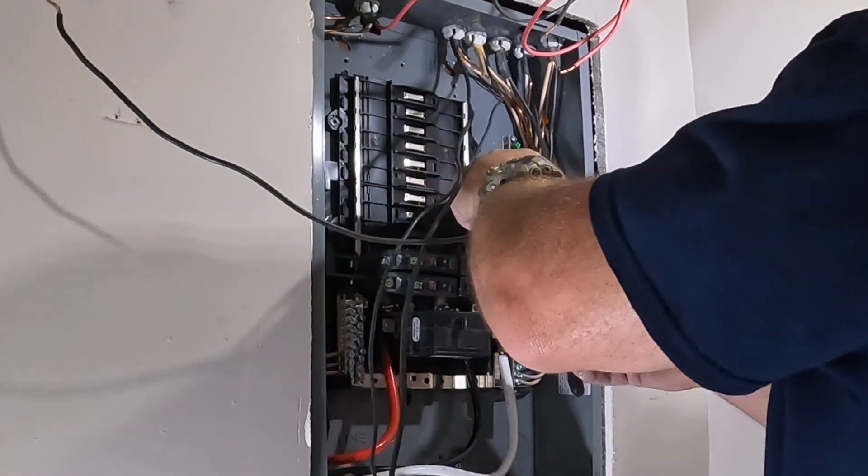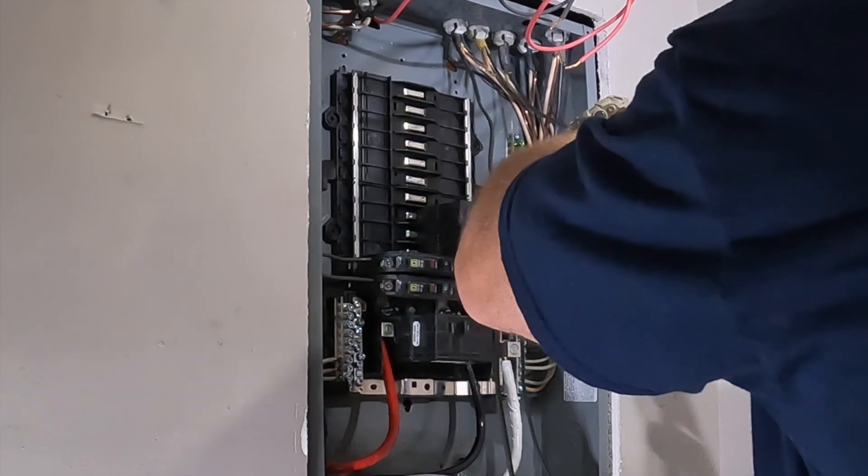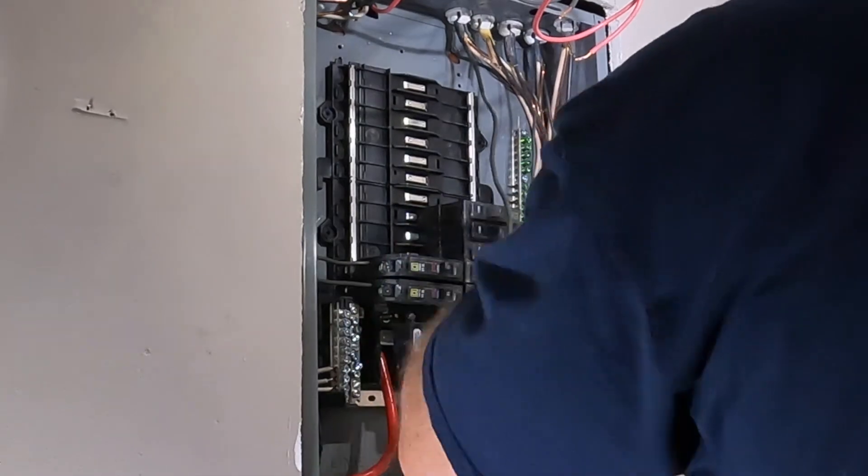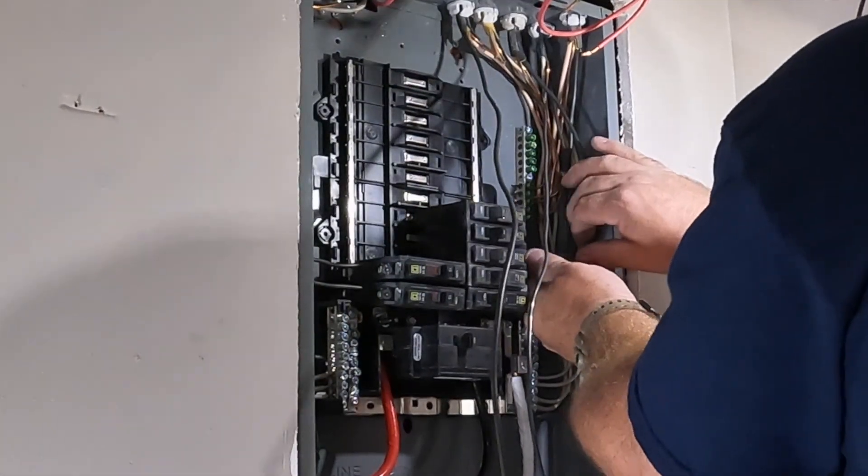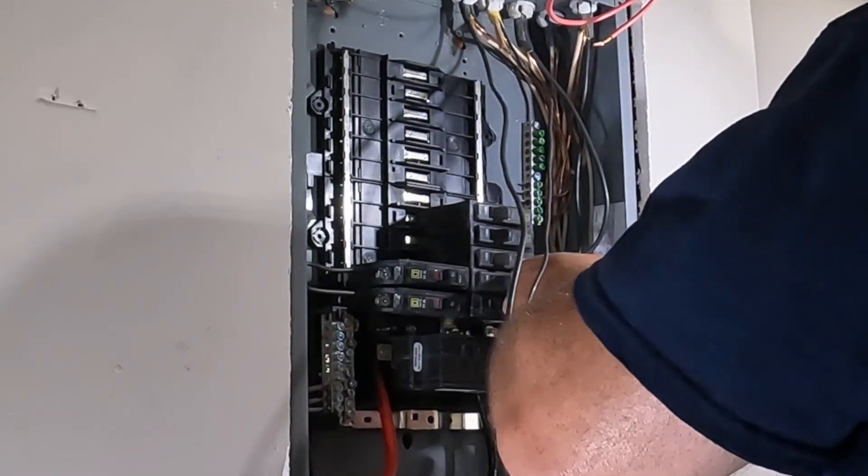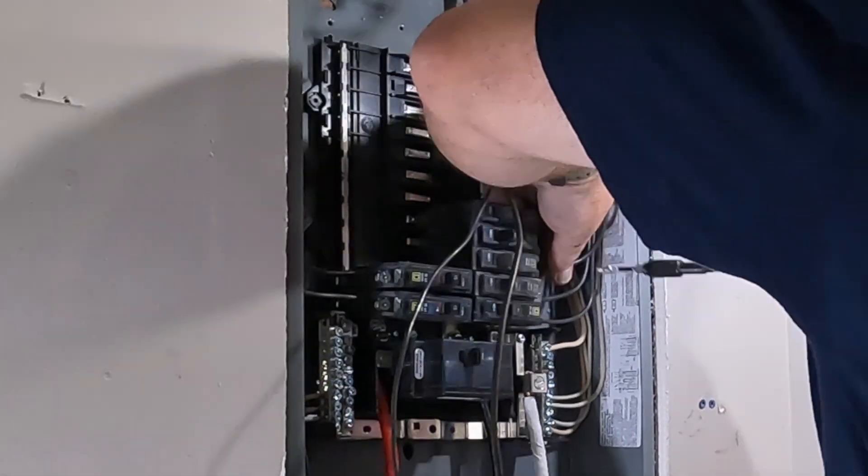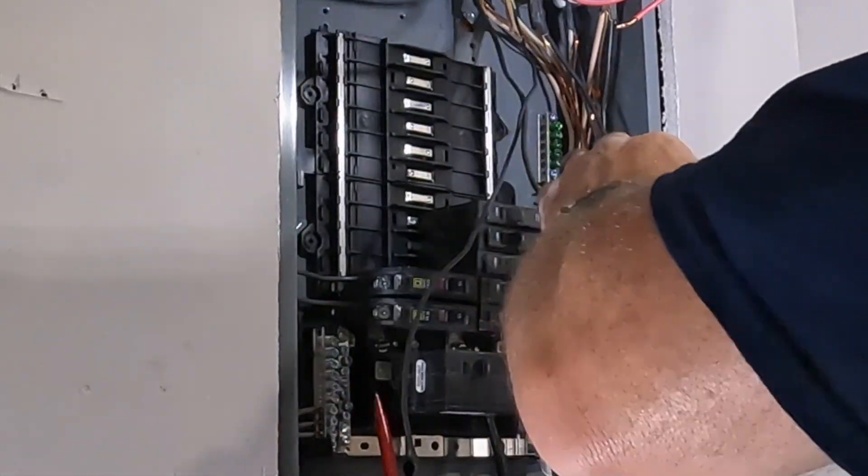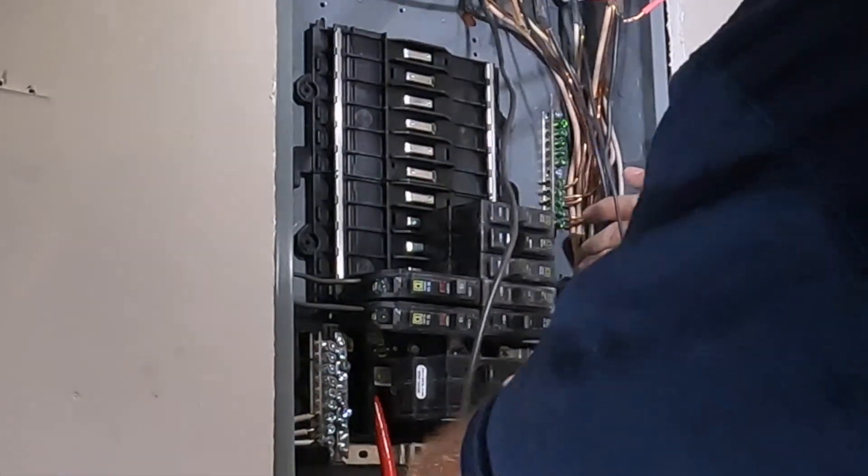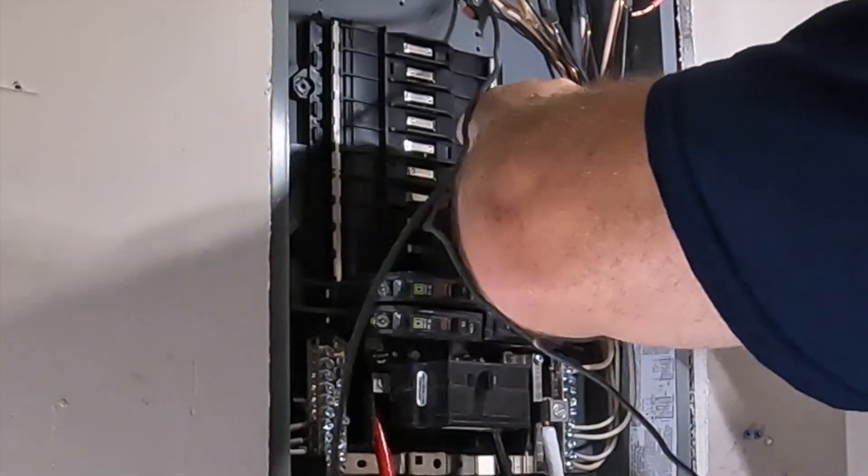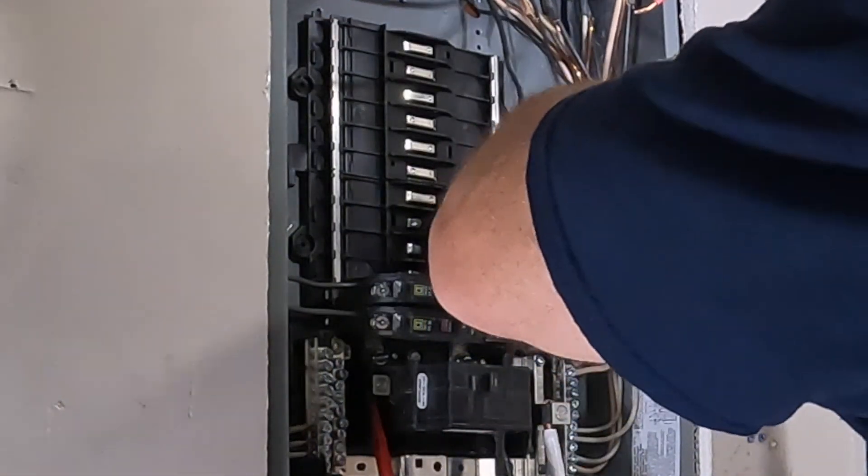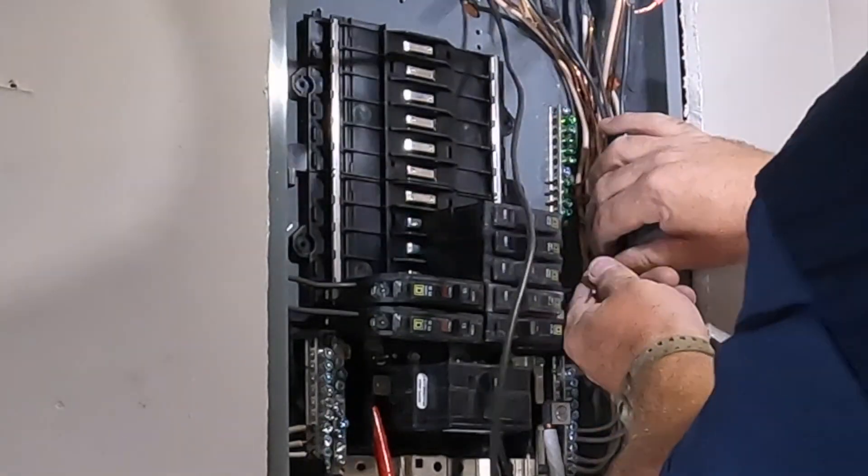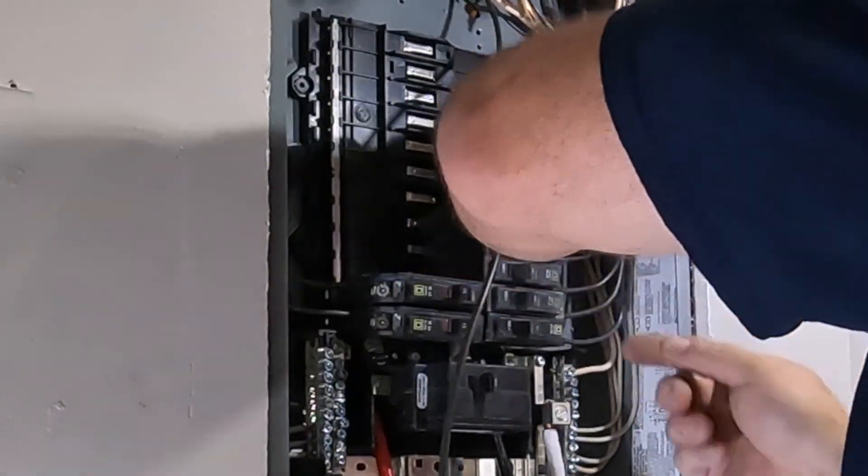I really like working with these QO panels, but as you can see here normally the main circuit breaker is on the top, but the conductors that were in place, the feeders, they weren't long enough. So I had to put this panel in with the main breaker at the bottom. Again, I should stress that this is not the main breaker at a main disconnect, this is a sub panel. Nonetheless, the feeder conductors were not long enough to put that main disconnect up at the top of the panel. So that's why it's at the bottom. But as you can see, those neutral terminals are right beside where the main breaker is, and if that's at the top of the panel and your branch circuits are coming in from the top of the panel, that makes for terminating your conductors very easy. So that's one of the reasons why I like the QO panels.